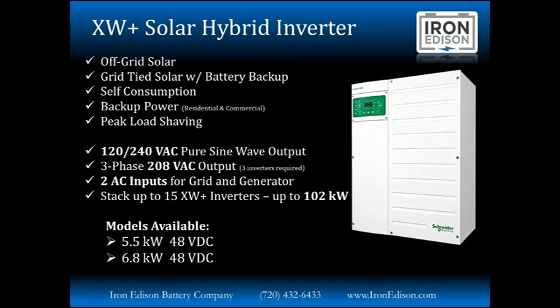In my opinion, the XW Plus inverter is one of the most feature-rich, one of the most versatile, and one of the easiest to install and set up. That's one of the main reasons why we love working with the Schneider equipment. Not only does it work, but it's able to work in such a wide range of applications, from one small system up to a very large commercial application. As we get further into this, you're going to see for yourself that the XW Plus really is kind of the Swiss Army knife of inverter systems. I really can't think of anything it won't do. It's quite an impressive unit.